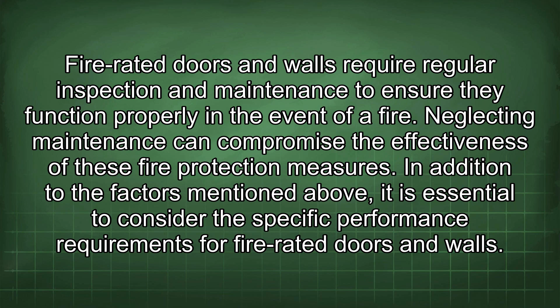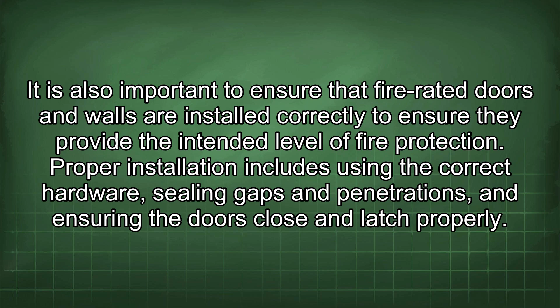In addition to the factors mentioned above, it is essential to consider the specific performance requirements for fire-rated doors and walls. Fire-rated doors and walls are classified based on their ability to withstand fire for a specific period, typically ranging from 20 minutes to 3 hours. The required fire resistance rating will depend on the specific application and the fire hazard associated with the electrical room. It is also important to ensure that fire-rated doors and walls are installed correctly to ensure they provide the intended level of fire protection. Proper installation includes using the correct hardware, sealing gaps and penetrations, and ensuring the doors close and latch properly.